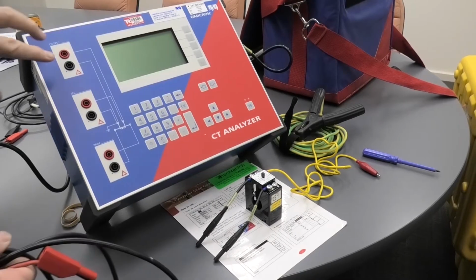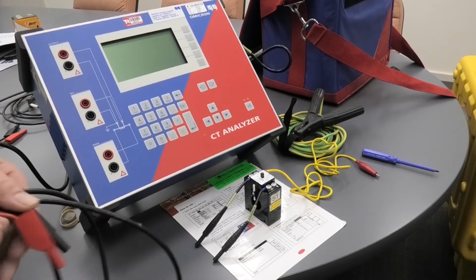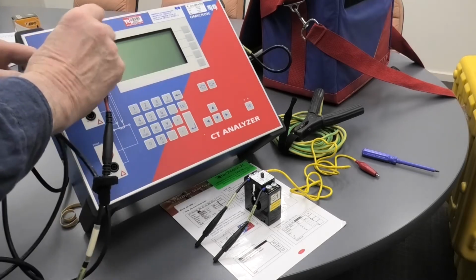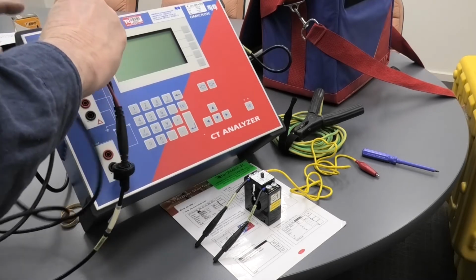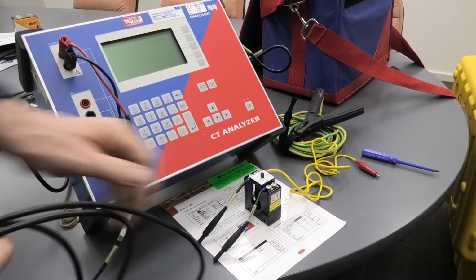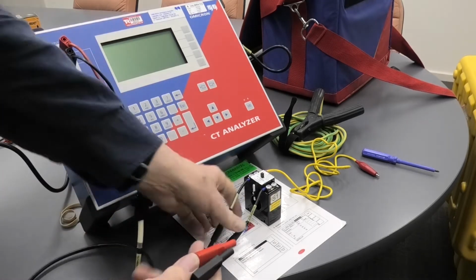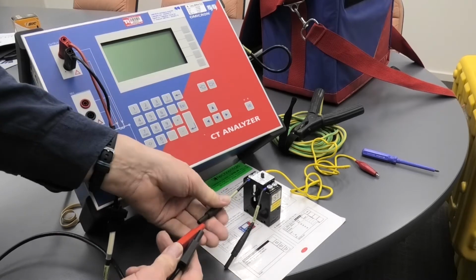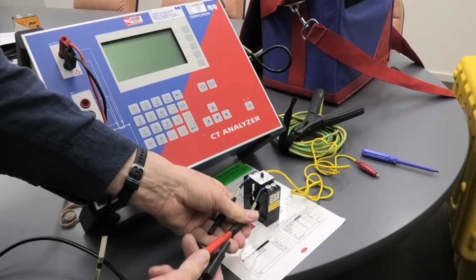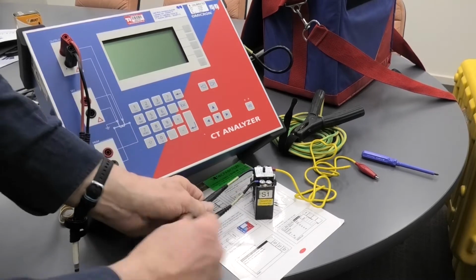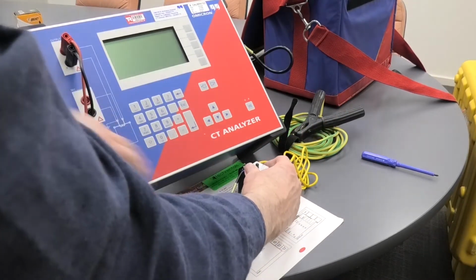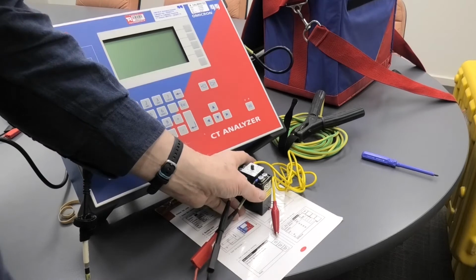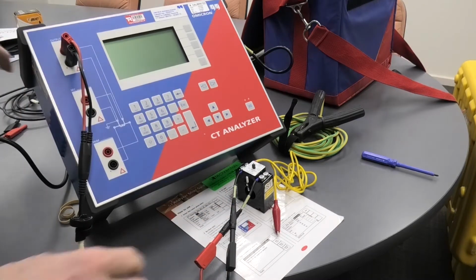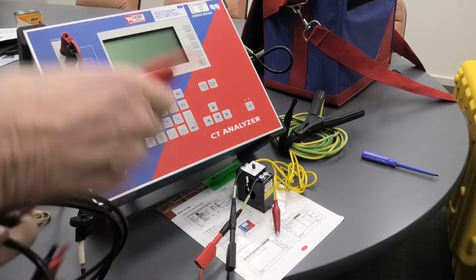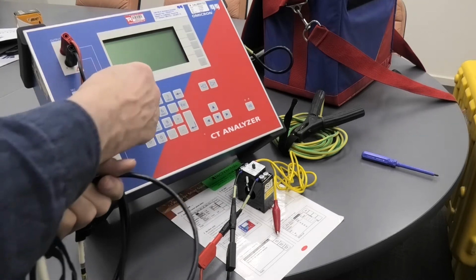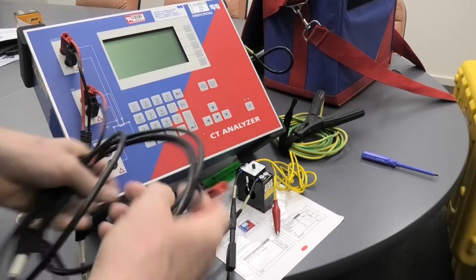Right, I'll need to wire the output of the CT, this red and white wire here, red and black wire here. So I'm going to bring those two down here, in here, and either side of the secondary side of this CT. So I'll connect this here to there. Now we've got a little earth line, which is down here, which will connect that up in a second. So we've got that there, and I'll connect the other side of this. Here's my secondary, to my secondary down here.